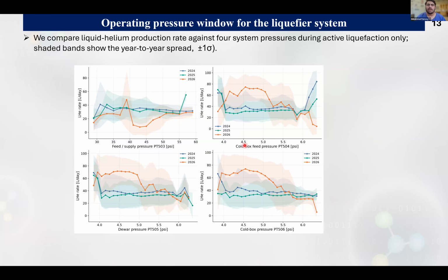The next one is the operating pressures. Normally we operate the cryocoolers from 4 to 6 psi, and we can see how these remain consistent within that range. These are the optimum parameters for our system, and it is working well. Hopefully the system will return to its normal optimum production rate after maintenance.